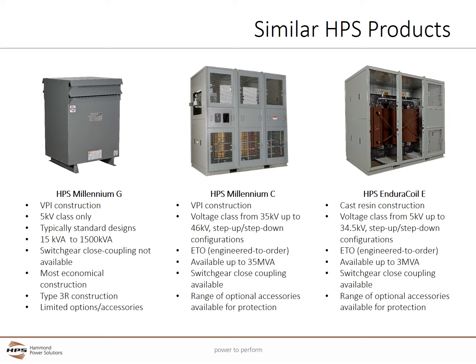The HPS Millennium C also uses VPI construction. It covers a wider voltage range from 5 kV up to 46 kV and is available in step-up or step-down configurations. The Type-C is engineered to order while the Type-G uses more standardized construction. Millennium C units have a wider range of kVA sizes up to 35 MVA. The Millennium C can also be close coupled to switchgear and has a wide range of optional accessories available for customization and protection.